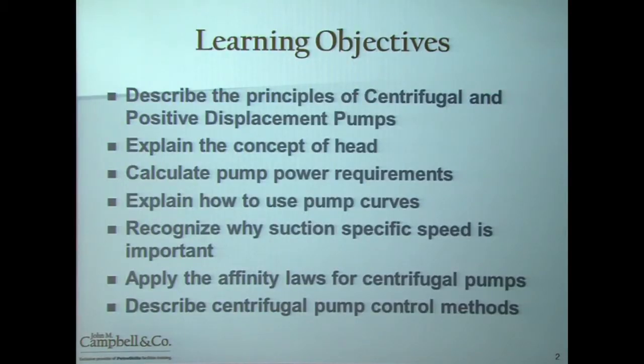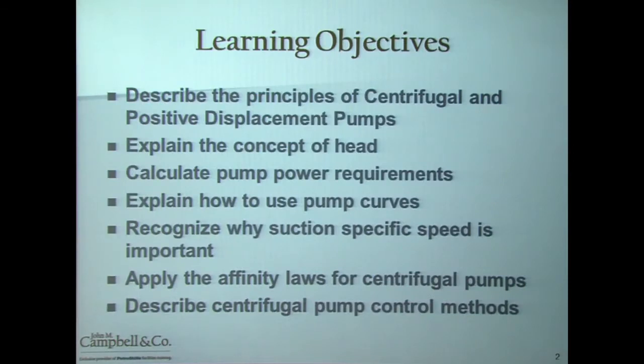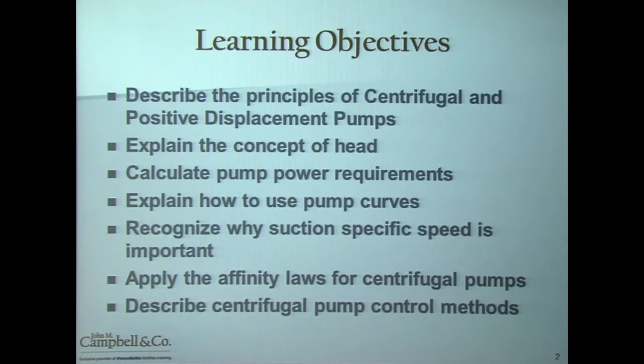You'll recognize why suction-specific speed is important — a concept that many facility engineers ignore or don't quite understand, and as a result, when a pump appears to be cavitating, they have lots of trouble trying to rectify or get to the root cause of the issue. You'll apply affinity laws for centrifugal pumps, which also apply to centrifugal compressors. And finally, in this section, you'll be able to describe centrifugal pump control methods.